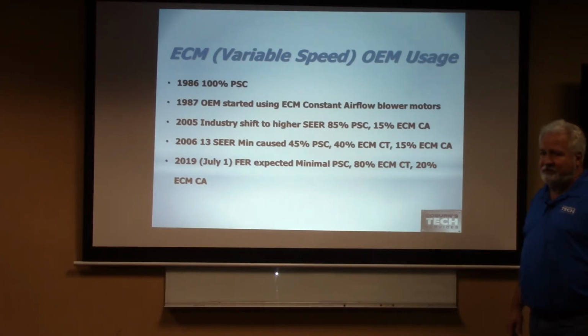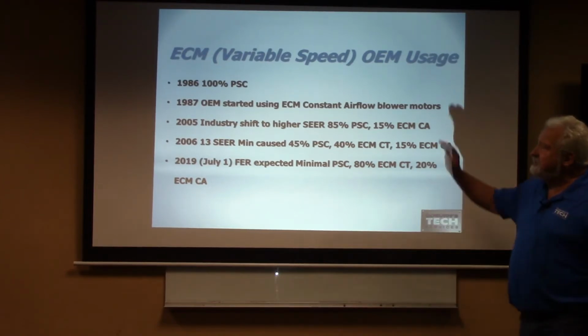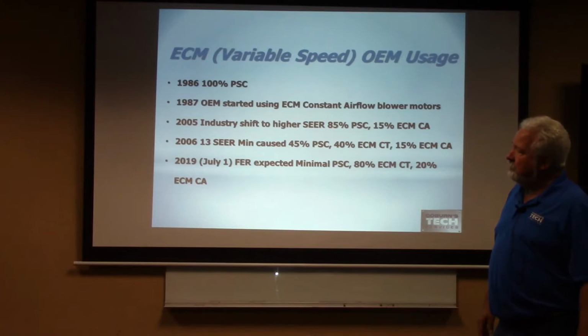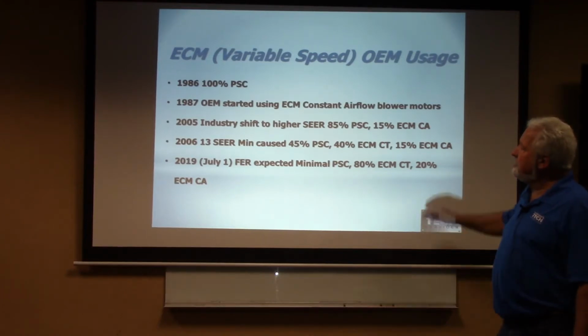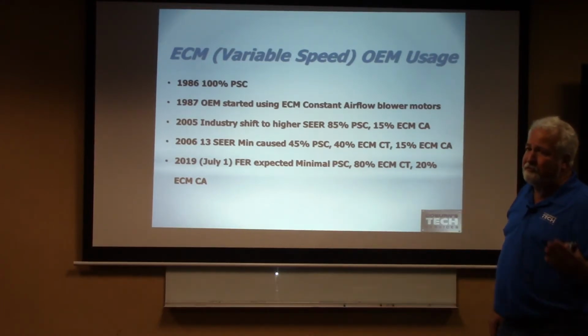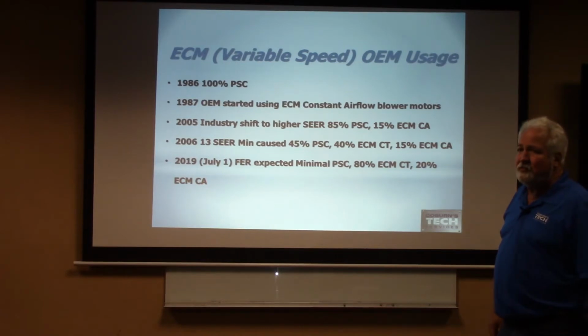Here's what's happening with ECM motors. You say, oh, well, Rick, I'm really not big into that. I like a PSC motor. I'm good there. That's fine. In '86, we were 100% PSC motors. In '87, the OEMs started coming out with a constant airflow motor. It was very expensive. We started seeing problems with moisture in those things. We had a lot of failures. They were very expensive to change out.